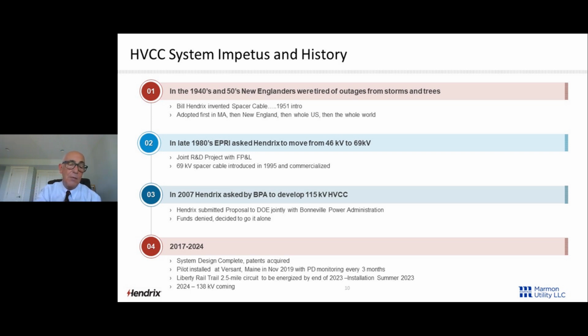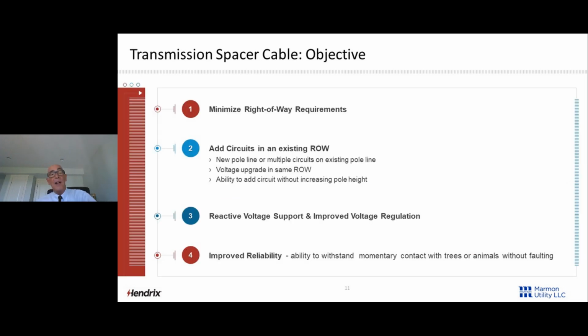2017 to 2024, I'm getting a little bit ahead of myself here, but system design was complete, patents acquired, and a pilot was installed at Versant, formerly Emera, in Maine. In 2019, with PD monitoring every 3 months, we just recently finished Liberty Utilities' rail trail 2.5 mile 115 kV spacer cable circuit. And we'll take a look at that. That will be energized soon. And in 2024, more good stuff coming. So that's exciting.